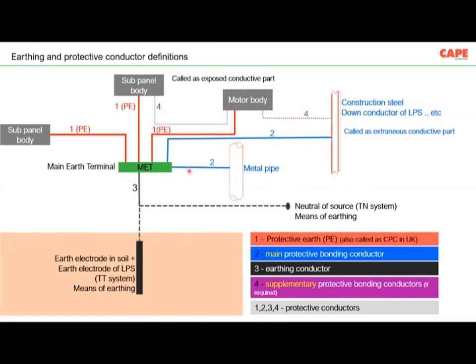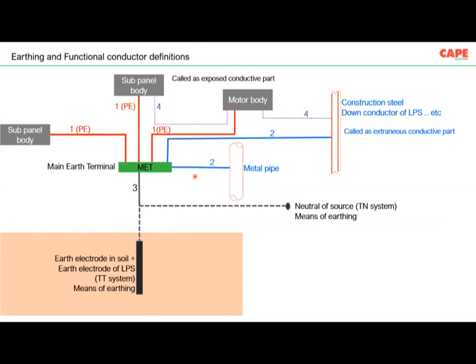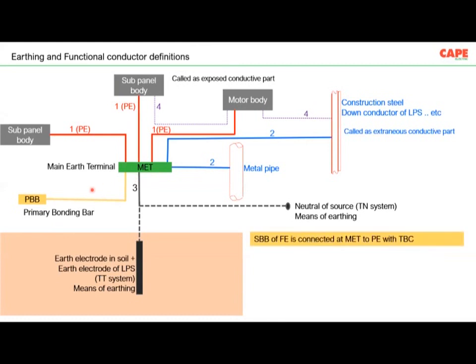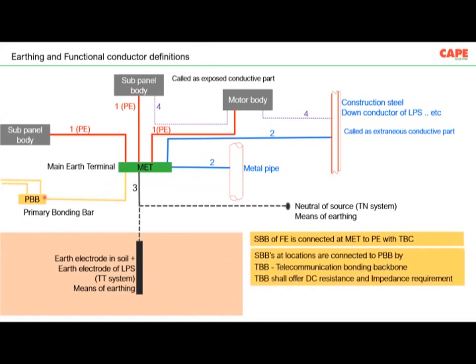Now, when we talk about protective bonding, let us say, for example, this connection number 2, which I am scrolling: the resistance of this wire, the sizing of the wire, the resistance of each joint, all these are important. Now, what about functional earthing? In the previous slide, I showed functional earthing, where all the equipment's FE terminals are connected to the PBB or SBB. Every building shall have a primary bonding bar, which is for the purpose of functional earthing.